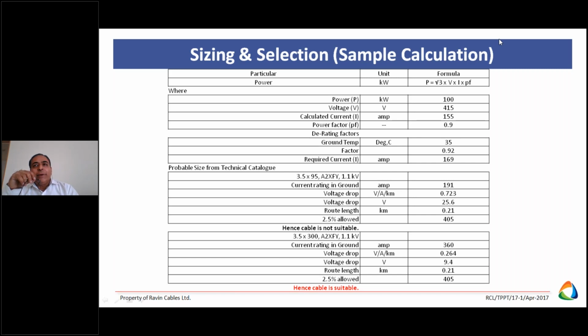Suppose we are using a cable in Srinagar where temperature is 20 degrees centigrade, and the same cable in Chennai where temperature is 40 degrees centigrade. Current rating is directly proportional to delta temperature. Delta temperature is conductor temperature minus surrounding temperature. Suppose conductor temperature is 70 degrees and environment temperature is 40 degrees: 70 minus 40 is 30, so delta is 30. In Srinagar, 70 minus 20 is 50, so delta is 50. Current rating is directly proportional to the square root of delta.